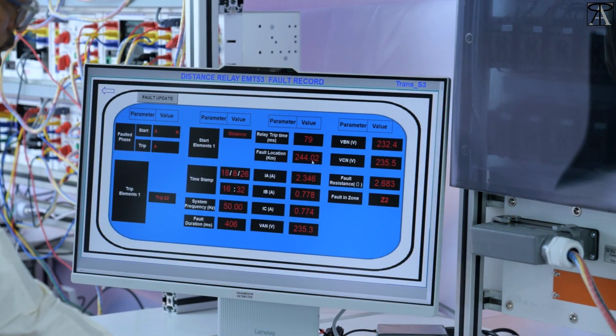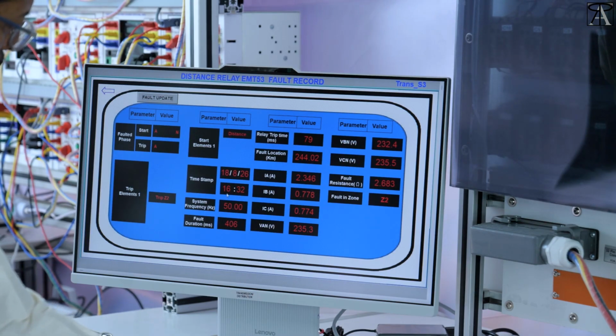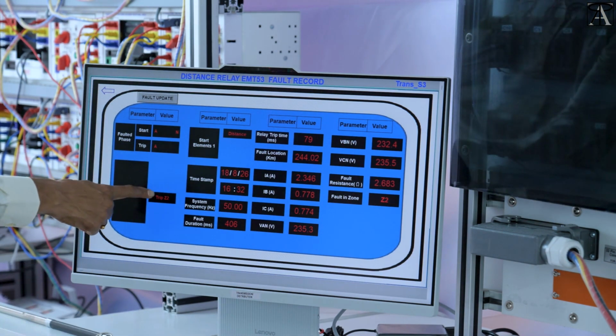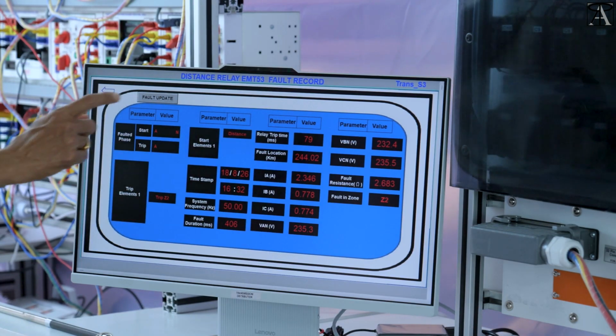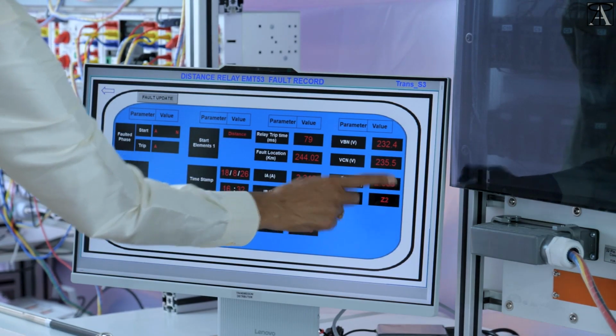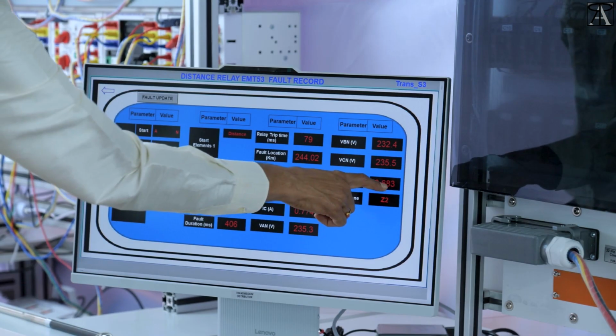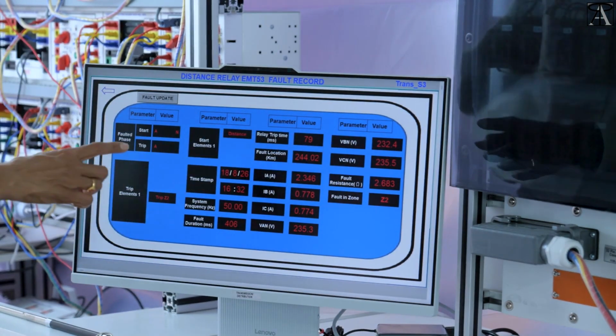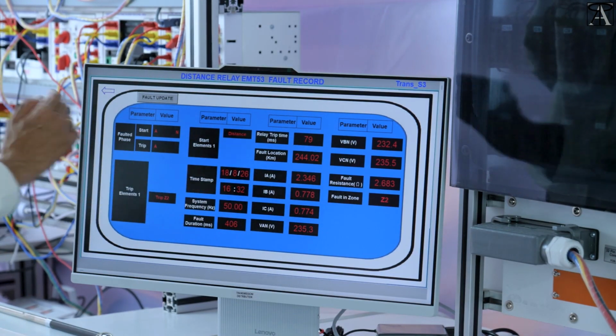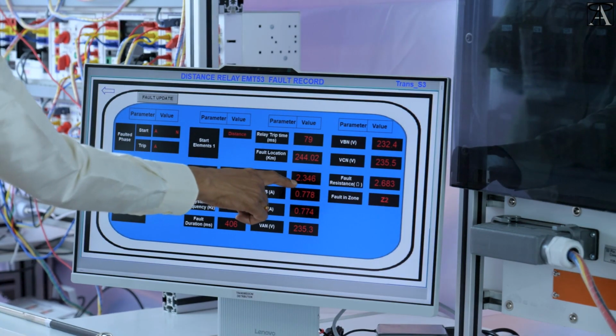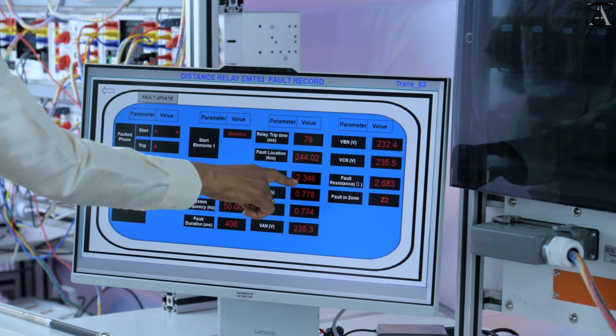Zone 2 fault at 244 kilometers. Previously 116 kilometers location. Now this is at 244 kilometers, and timestamp is 4:32, 16.32, and date is 18/8/26. And trip fault is zone 2. Trip is because of one phase and with neutral. Fault zone is zone 2. Fault resistance also you can measure, 2.6 ohm. Voltages and currents you can check. Once we create the fault, that is the reason A phase is getting more current.